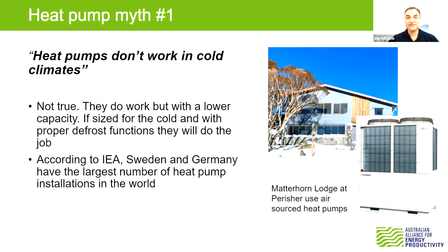If you look at reports from the likes of the IEA, you'll see that Sweden and Germany have the largest number of heat pump installations anywhere in the world. Chris, you've been following those installations over there as well. Yeah, and the reason they can do them effectively in cold climates is that they cleverly use as much heat recovery as they can - rather than trying to source heat from sub-zero air, it's much better to recover exhausted heat from the building or from a warm water source somewhere. They make very good use of that, and in those situations, even in a cold climate, a heat pump can work very well.